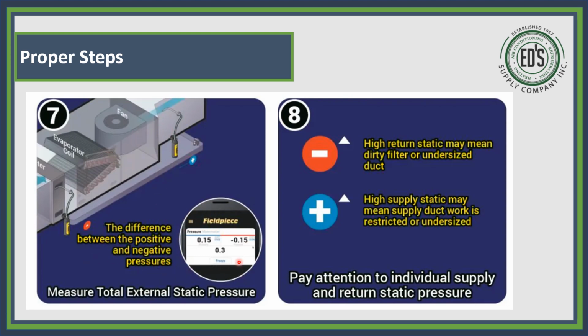Now, they have the Fieldpiece Bluetooth dual manometer. That's what you see here. And they will show up as a minus 0.15. And the positive will be on this side. And when you add those together, you get 0.30. Okay. Sometimes you flip it around and it'll zero this out like they were subtracting each other. You don't want that. You've got to have that added together.